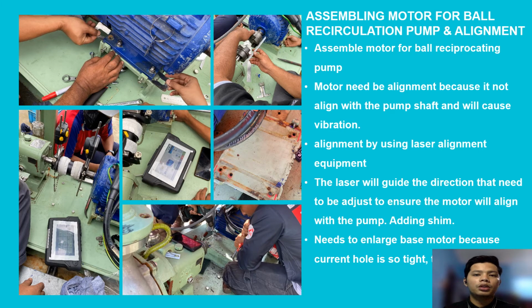In order to assemble the motor, we need to ensure the motor is connected in the center position with the gearbox shaft. The motor can run smoothly with low vibration when we install it in the correct way. During assembling, we need to enlarge the hole for the motor base because the hole is small and alignment cannot be done. For this activity, we use laser alignment as our equipment. The laser will guide us on which direction to adjust and where to fix, to ensure the motor is aligned with the gearbox shaft.